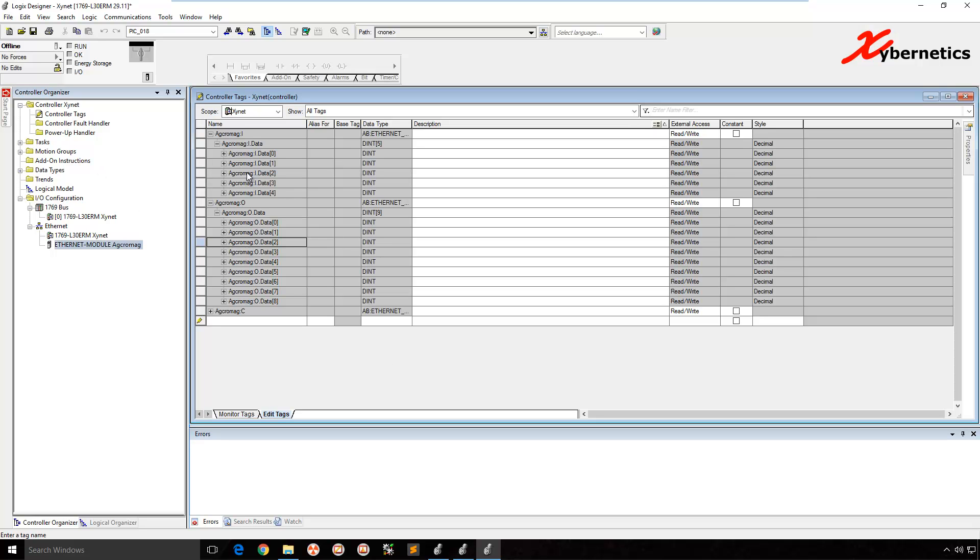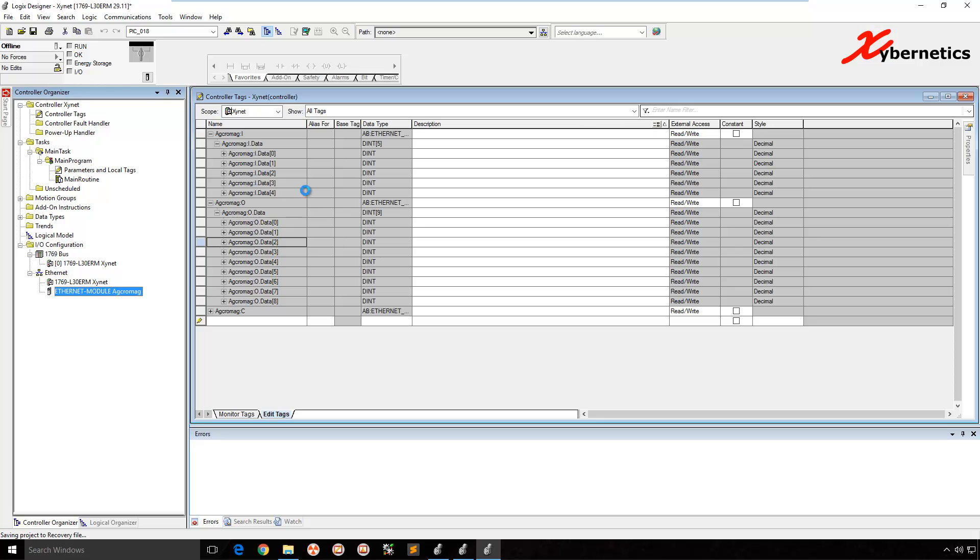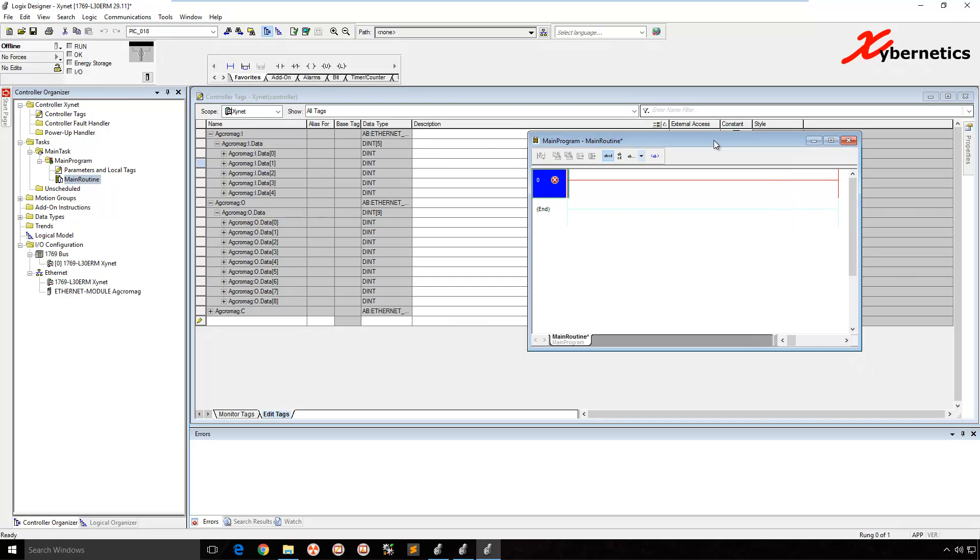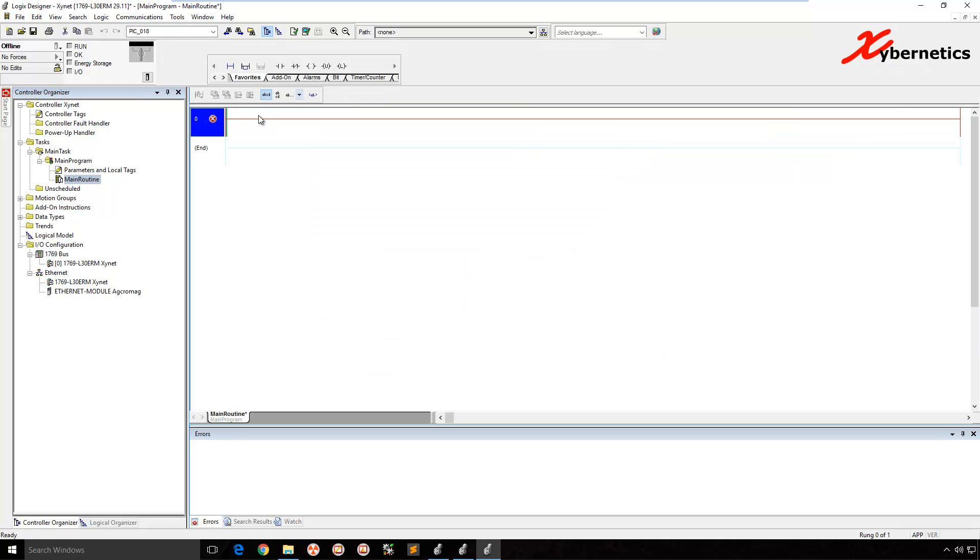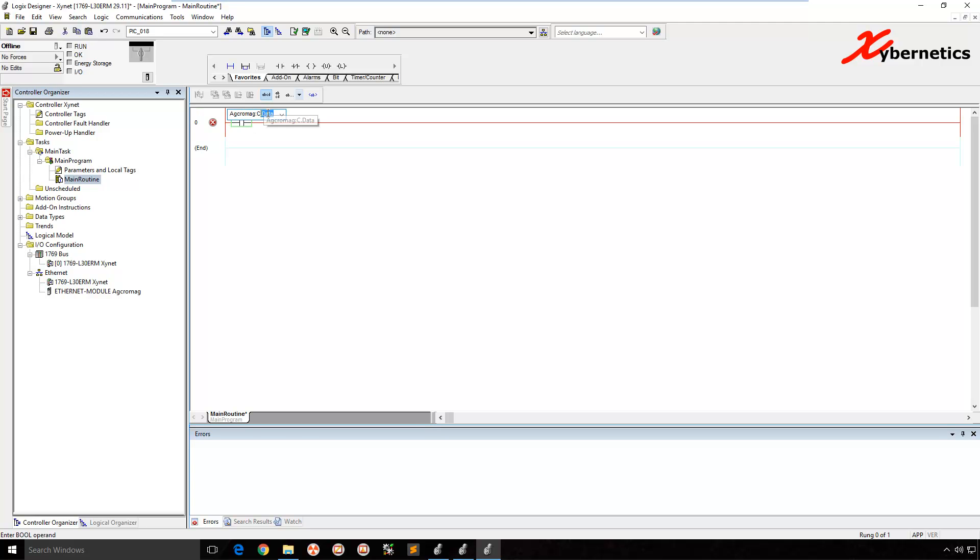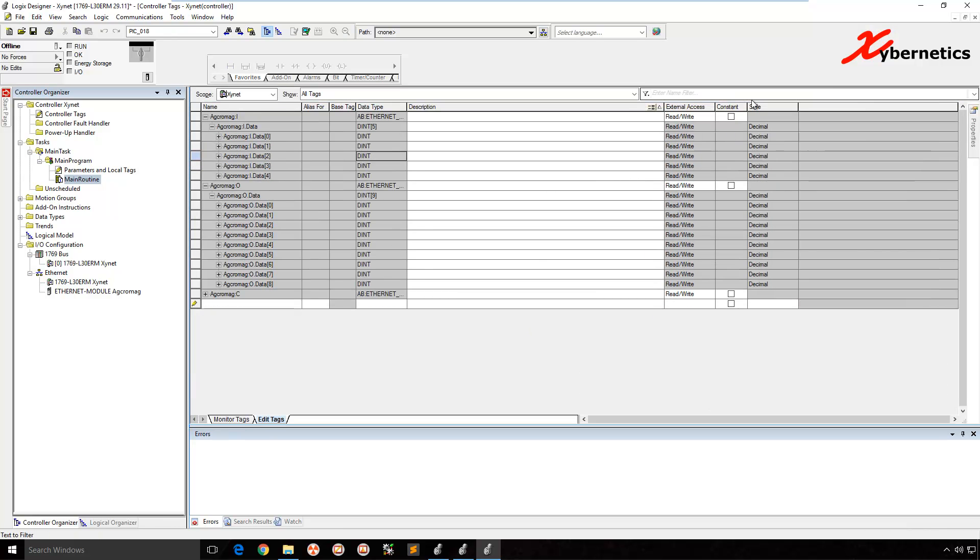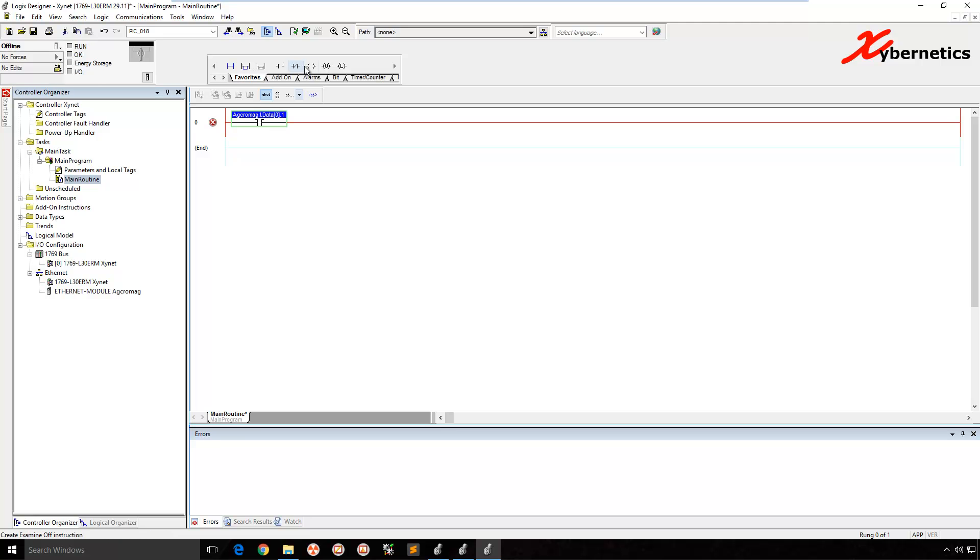And you also have to be able to configure your assembly input and output and the size to get that thing done. And once you're ready, write your program to access it. You probably know if you have done a program in Allen Bradley before. So I'm just going to create a rung. Drop it in here. Call it Acromag:I.Data, say input. Acromag:I.Data, say zero, and then you want to trigger an output. Output would be dot, say one. Like that. That's how you'll be using your AcroMAG meter here to read and write it back.